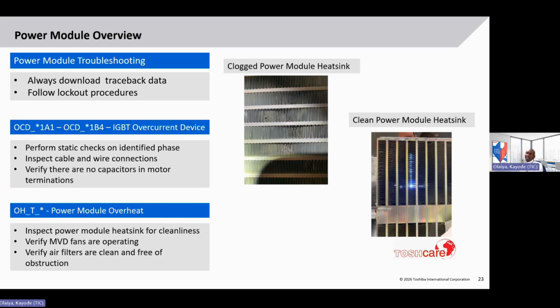Following the testing and troubleshooting theme, I've included a slide here on what to do on just 2 faults that you could encounter in the field. First step, anytime you have a fault on the drive, is to always download traceback data. You want that data recorded because the drive has a limited number of registers to store faults. And so eventually the data will be overwritten. So if you store it, then you'll have it for future reference.